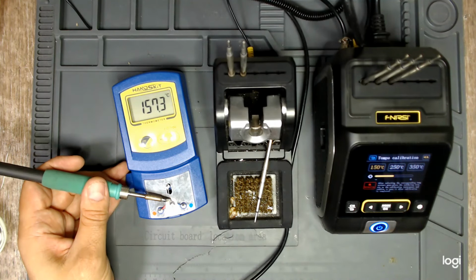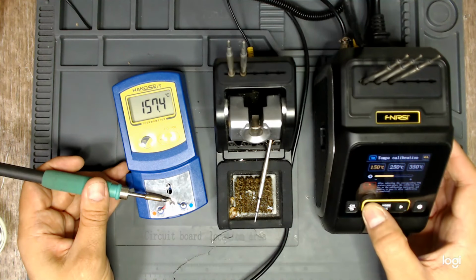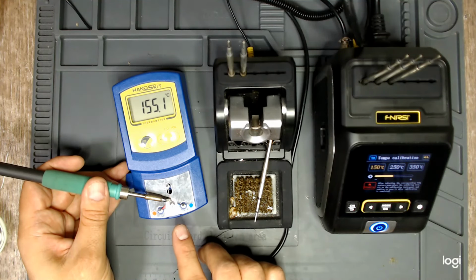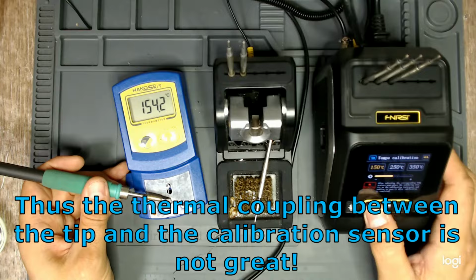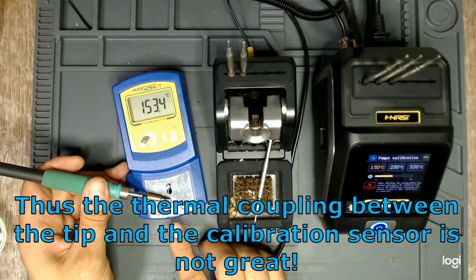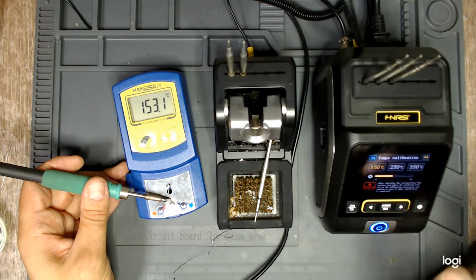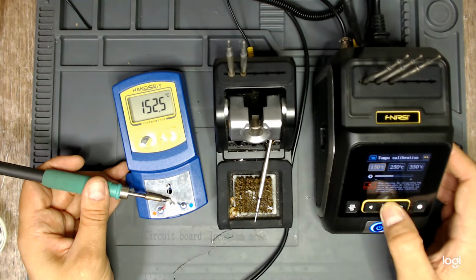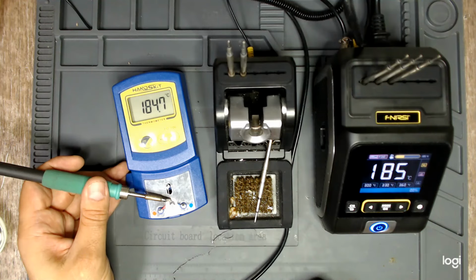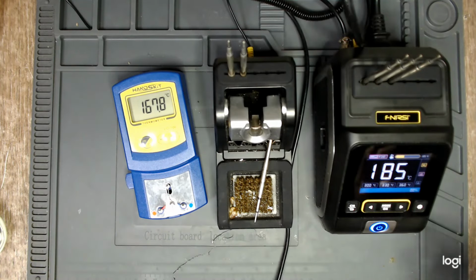The calibration seems off at 150 degrees. Seems indeed off, so let's fix it. It is more difficult to calibrate at such a low temperature. I do not have low melt solder, the type of solder that melts at below 100 degrees C. This makes it more difficult to make good contact with the temperature sensor. Let's leave it at that. There we go. 184 degrees C, 185. Works for me.